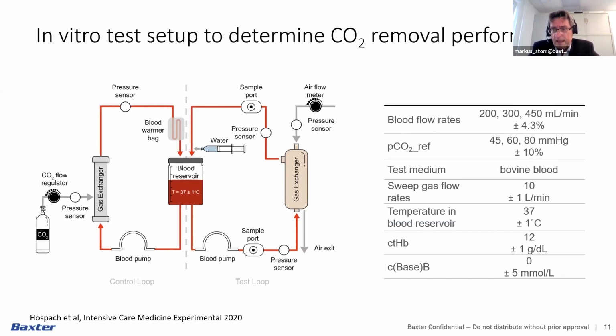So we used bovine blood in the circuit. You see that the test circuit comprised a central reservoir filled with the blood, as well as two loops. The control loop had a gas exchanger connected to a CO2 supply, which was used to achieve and adjust the target inlet PCO2 levels. The control loop was connected to the test loop via the central reservoir. And in the test loop on the right, the test device was positioned to determine the CO2 removal capacity.